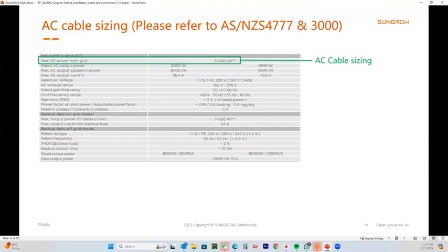On the 10 kilowatt AC cable sizing, the maximum AC power from the grid here is 14.5, which is 63 amps. And for the same reason, you could be charging the battery and you could be fully maxed up backup power at the same time. We refer to that as AC pass-through.